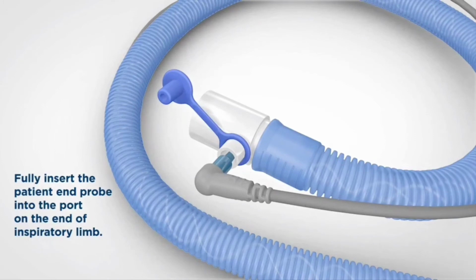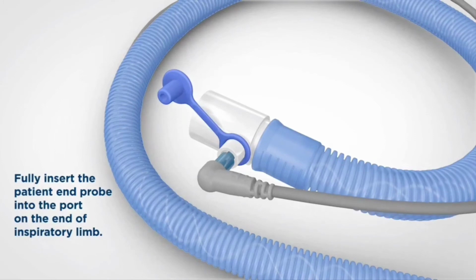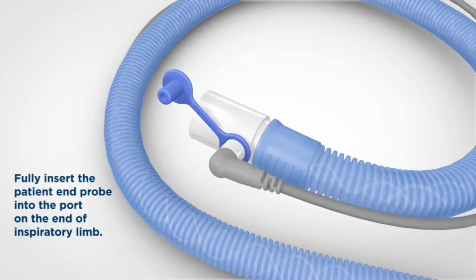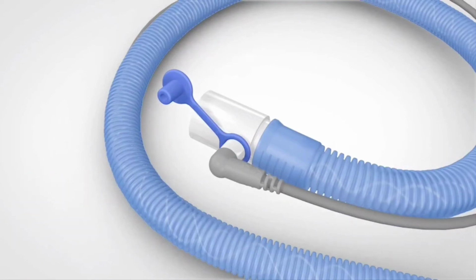Insert the temperature probe into the temperature probe port at the patient end of the inspiratory limb. Again, it is important for correct function of the system that the probe is inserted fully. You'll notice that there is no blue probe plastic showing outside the circuit, and the grey plastic is seated against the probe port.